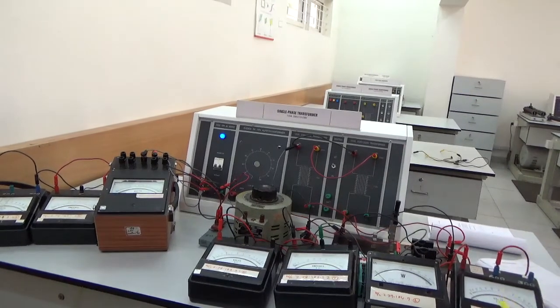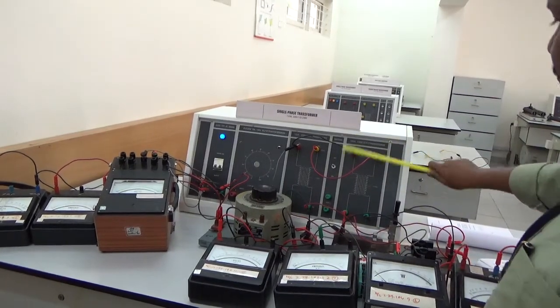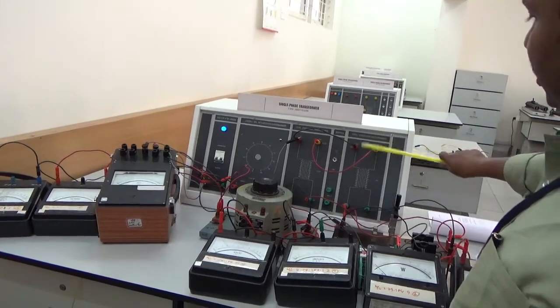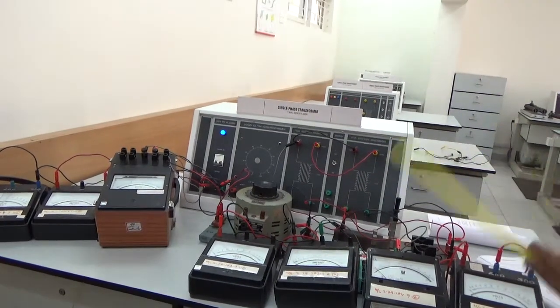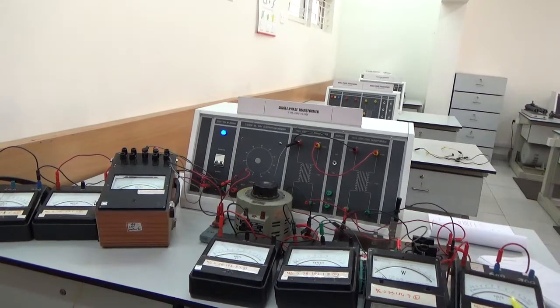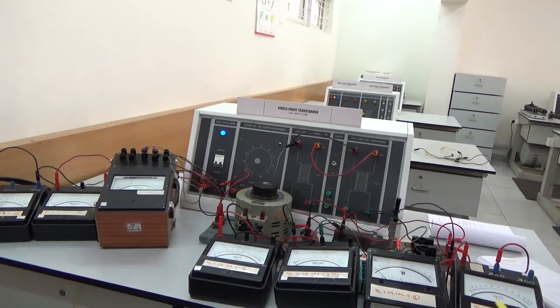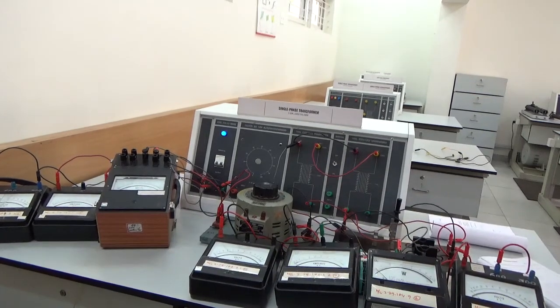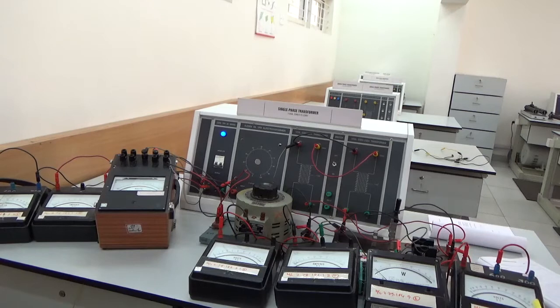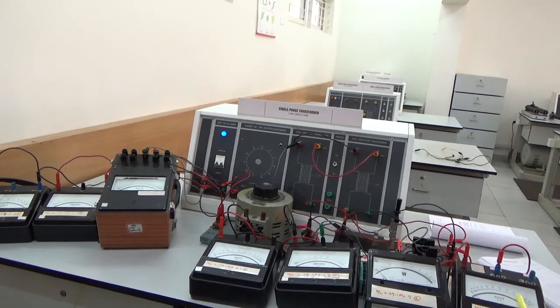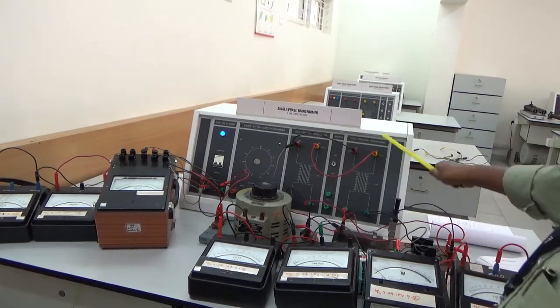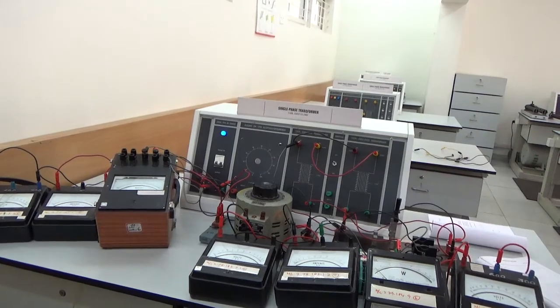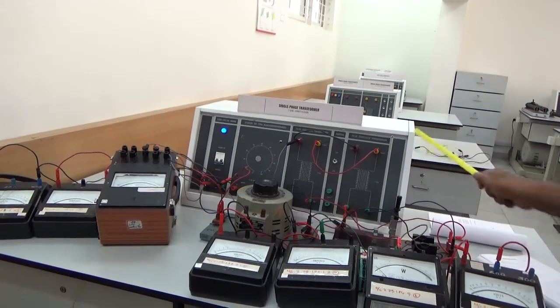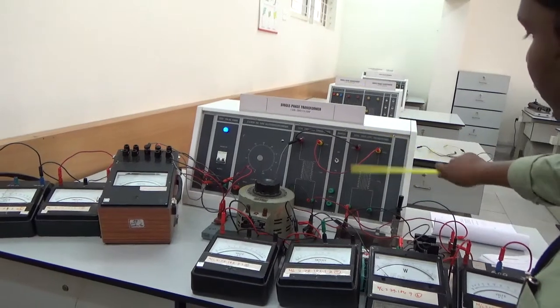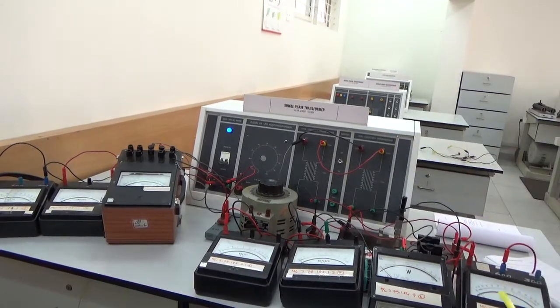That is only 0 if the secondary voltages of the two transformers are in phase with each other. Otherwise, if the supply is closed and it shows double the voltage, 230 plus 230, that is 460, then it means the voltages are out of phase. In that case you have to switch off the set, interchange the connections, and make the voltage 0.